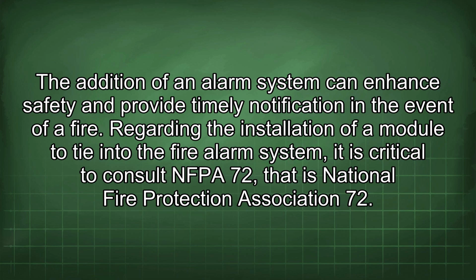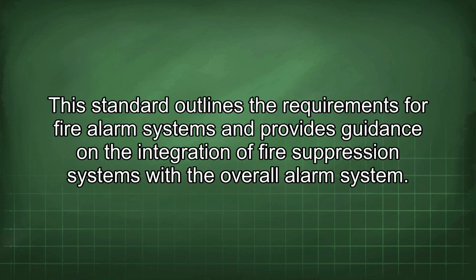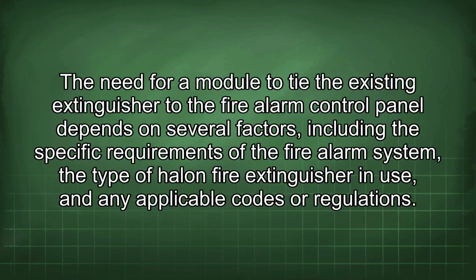Regarding the installation of a module to tie into the fire alarm system, it is critical to consult NFPA 72, that is National Fire Protection Association 72. This standard outlines the requirements for fire alarm systems and provides guidance on the integration of fire suppression systems with the overall alarm system. The need for a module to tie the existing extinguisher to the fire alarm control panel depends on several factors, including the specific requirements of the fire alarm system, the type of Halon fire extinguisher in use, and any applicable codes or regulations.